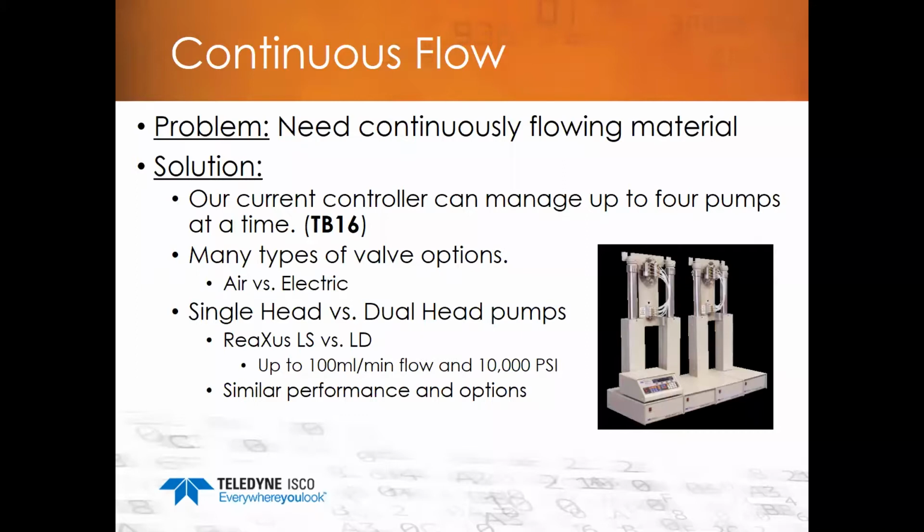Now, if the problem is continuous flowing material, great. You can put two pumps together and you can have a continuous flow, or you can get dual-headed pumps that have continuous flow. So you definitely have options when you look at the style of pump. But a bit of a different twist is that Teledyne ISCO has the ability, with their current-day controller, to manage 4 pumps at a time.